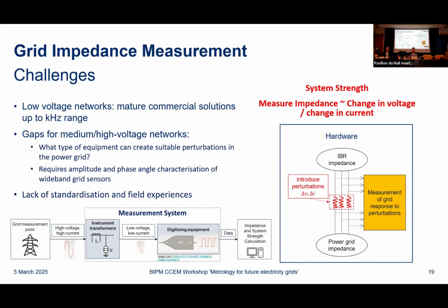In principle, measuring grid impedance is relatively simple. In simplified terms, you basically need to measure the change in voltage divided by the change in current. For low voltage networks, there are mature commercial solutions going into the kilohertz or hundreds of kilohertz. So it's something that's quite well established, although not necessarily standardized. But once we go to medium and high voltage networks, which is where especially these transient oscillations occur, there are a lot of questions, because in order to measure the impedance, you need a disturbance, a perturbation, and then you measure the response. So there's a question as to how you generate this type of perturbation.